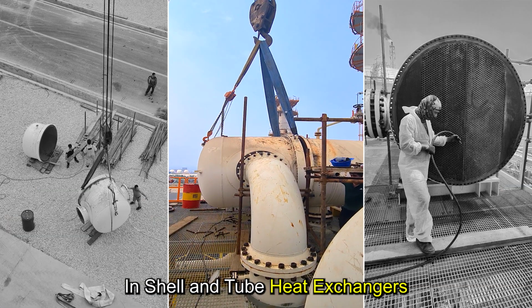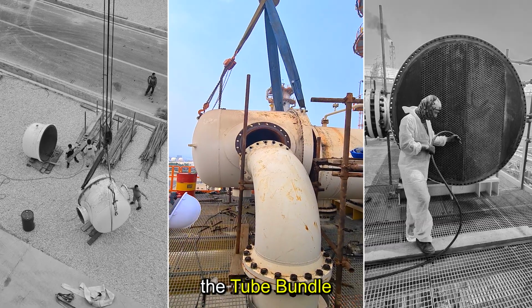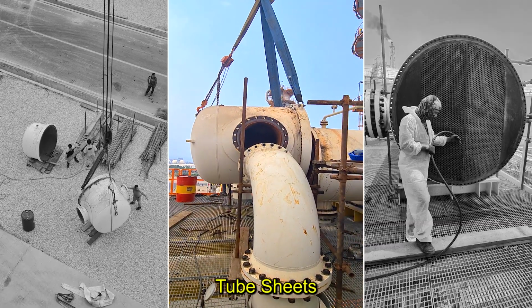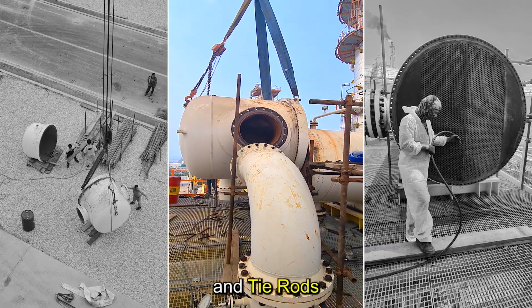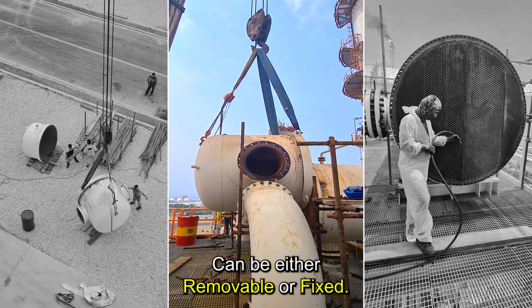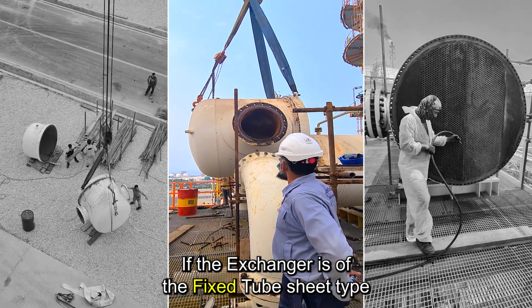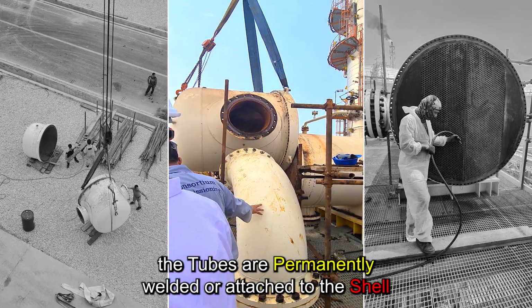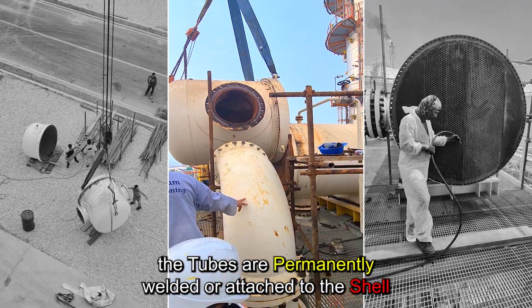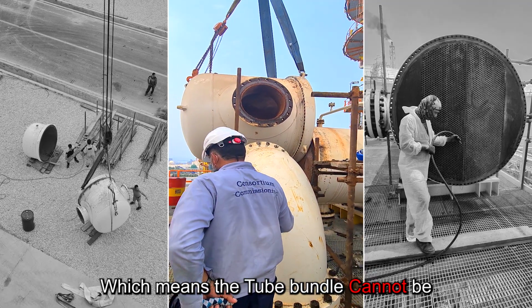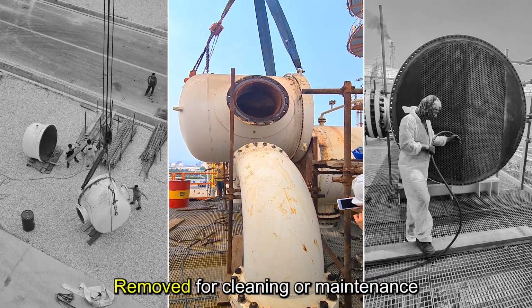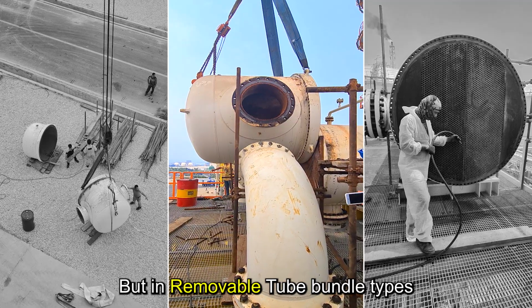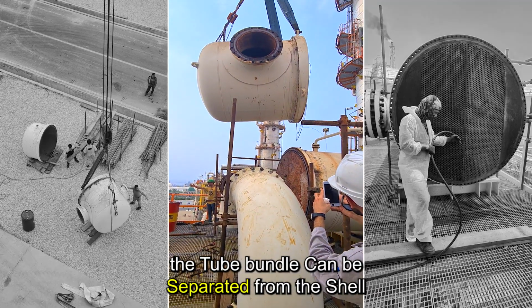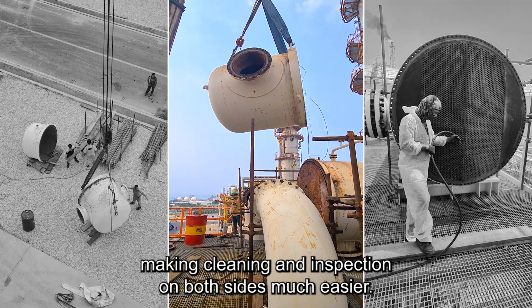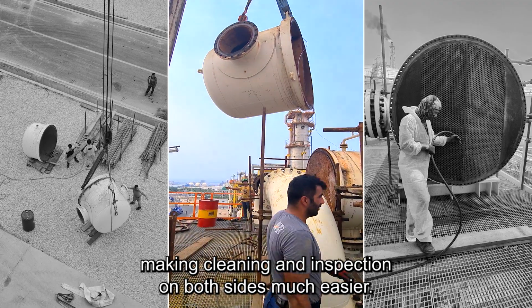In shell and tube heat exchangers, the tube bundle, which includes the tubes, tube sheets, baffles, and tie rods, can be either removable or fixed. If the exchanger is of the fixed tube sheet type, the tubes are permanently welded or attached to the shell, which means the tube bundle cannot be removed for cleaning or maintenance. But in removable tube bundle types, the tube bundle can be separated from the shell, making cleaning and inspection on both sides much easier.